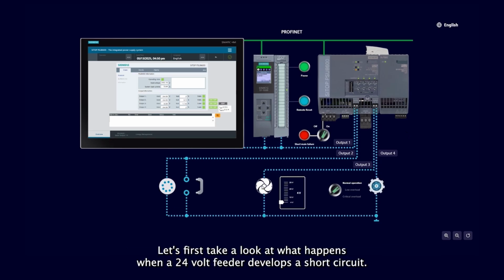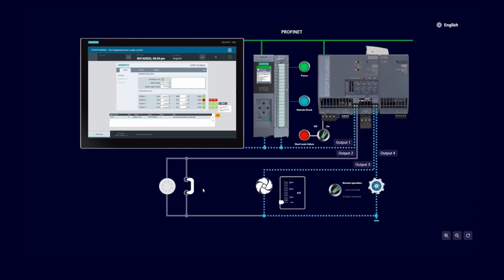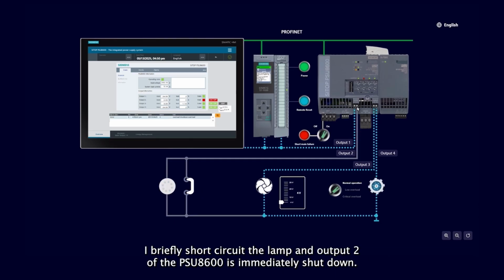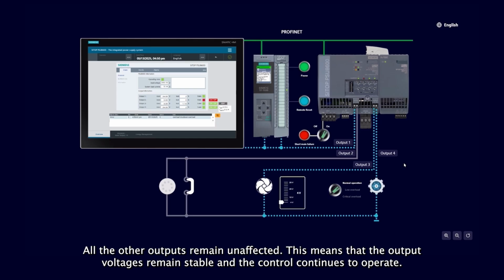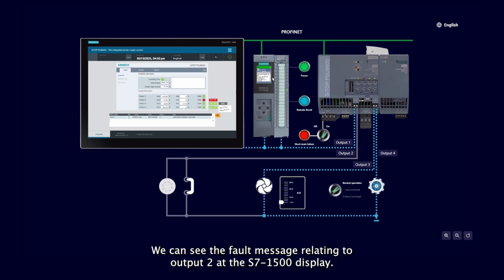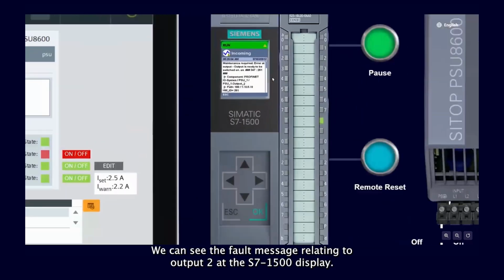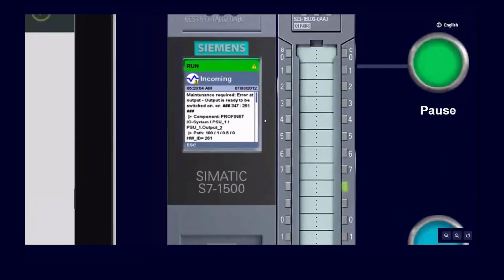Let's first take a look at what happens when a 24-volt feeder develops a short circuit. I briefly short-circuit the lamp, and output 2 of the PSU8600 is immediately shut down. All the other outputs remain unaffected. This means that the output voltages remain stable and the control continues to operate. We can see the fault message relating to output 2 in the S7-1500 display.